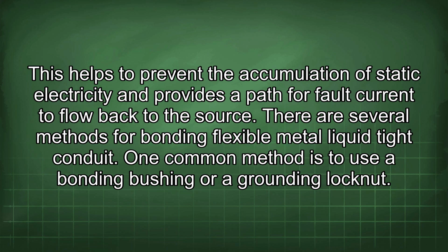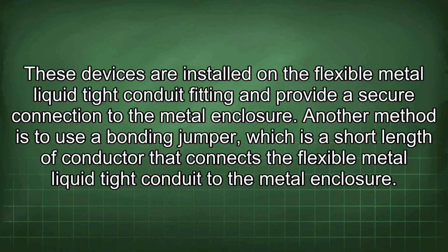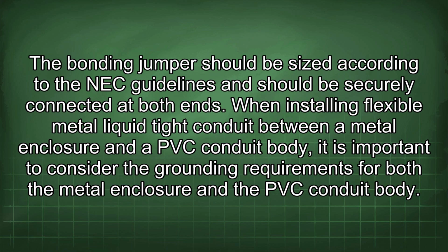One common method is to use a bonding bushing or a grounding lock nut. These devices are installed on the flexible metal liquid tight conduit fitting and provide a secure connection to the metal enclosure. Another method is to use a bonding jumper, which is a short length of conductor that connects the flexible metal liquid tight conduit to the metal enclosure. The bonding jumper should be sized according to the NEC guidelines and should be securely connected at both ends.